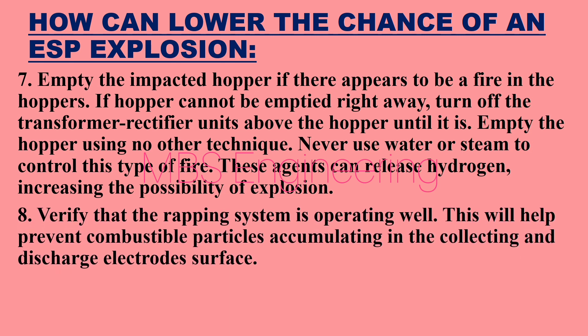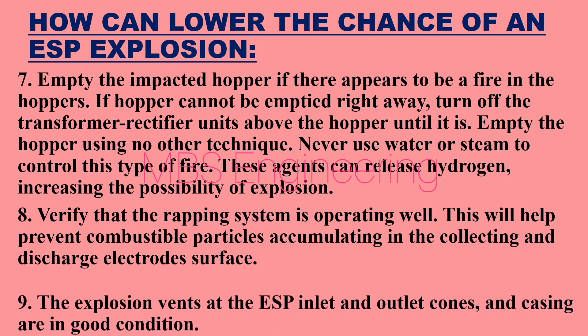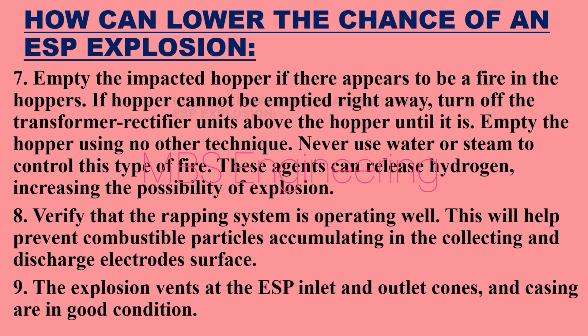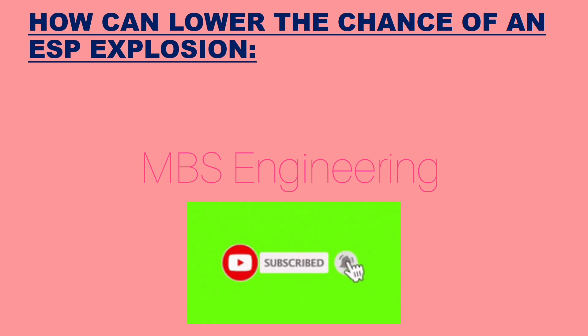Point 8: Verify that the rapping system is operating well. This will help prevent combustible particles from accumulating on the collecting and discharge electrode surfaces. Point 9: Ensure the explosion vents at the ESP inlet and outlet cones are in good condition.